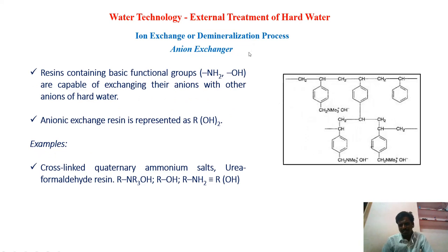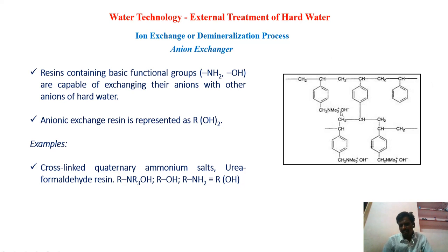The next type is the anion exchanger. These anion exchangers also have a linear polymer chain resin. These resins carry OH⁻ ions with the functional group, which is a quaternary ammonium salt. That OH⁻ can be exchanged with negatively charged anions from the water — the OH⁻ ions are released and chlorides or sulfates get accommodated. That is called anion exchanger resin.